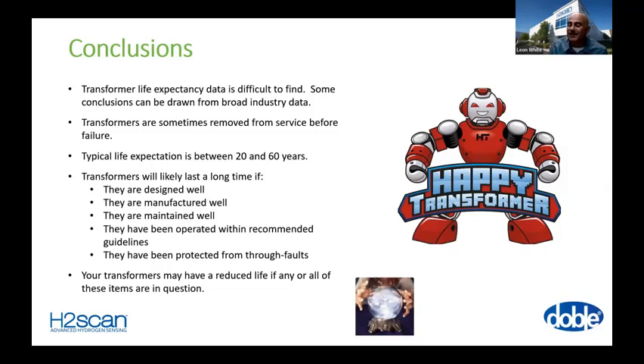In general, again, depending on the criticality of the transformer, you're going to install monitoring appropriate for the criticality of the asset. And most of the time, the value of the transformer is very small compared to the process or the revenue at stake if you lose that transformer. And so most utilities, large transformers, are installed with redundant systems so that if one fails, others in the system can pick up the load. But as you move farther and farther down to the distribution and so forth, that may or may not be the case.